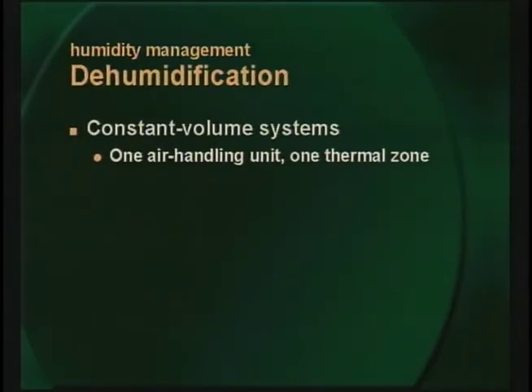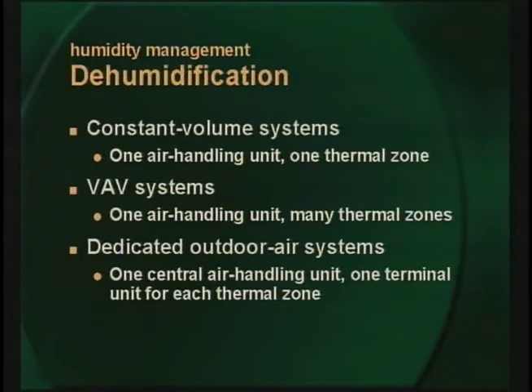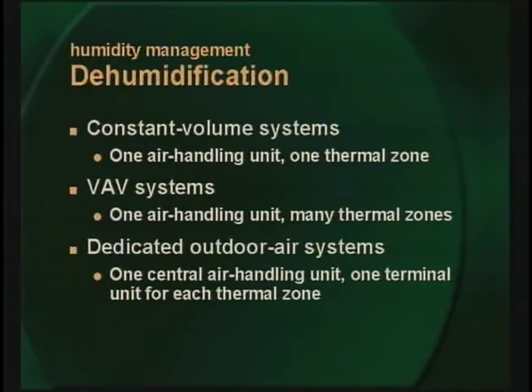The VAV system is also widely used and is often the most forgiving system in terms of dehumidification. This system includes one air handling unit delivering a mixture of outdoor air and return air at varying volume and constant temperature to many thermal zones, with a VAV terminal unit to modulate the airflow to each zone. Finally, the dedicated outdoor air ventilation system is usually applied with local constant volume terminal units such as water source heat pumps or fan coil units. One central air handler preconditions outdoor air for ventilation and delivers it to local units or directly to each thermal zone. Each of these systems deserves a separate broadcast. Today we'll focus on the very common and very troublesome constant volume system.